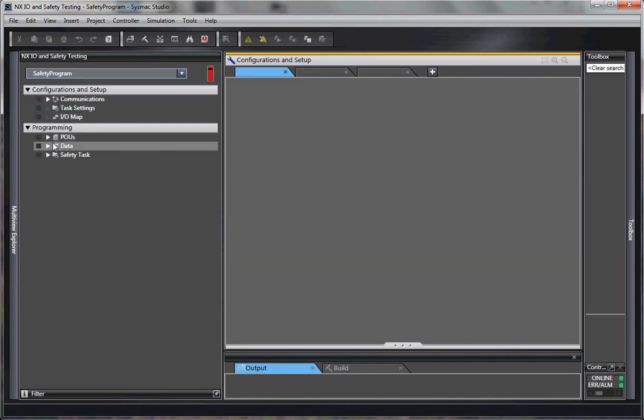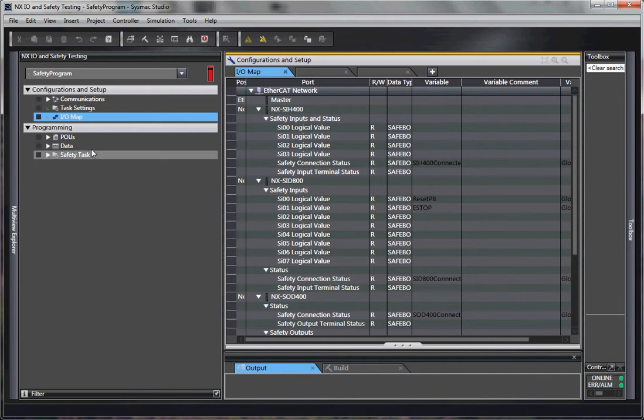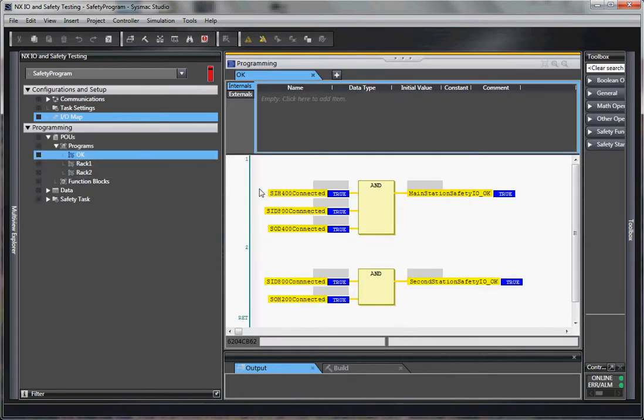We go to the safety program and the first thing we notice is that each I.O. card, each safety I.O. card has a safety connection status bit. There's one here, one here. We give them names and we add a piece of program. These are all my status bits for the safety I.O. in node 1. And when they're all on, I enable this group because this group is most likely used for safety on the main station.